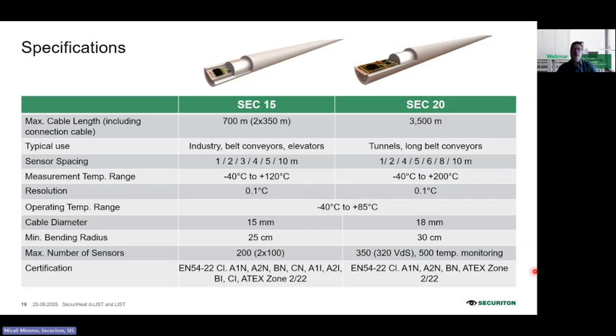We have two types of sensor cable. We call them SEC 15 and SEC 20. The SEC 15 is a little bit thinner, like 15 millimeter diameter. And here we have a limited number of sensors. They are maximum 200 sensors, or we can reach maximum with this cable 700 meters. So it means you need one controller for 700 meters, but you can expand. You can have several controllers in the same tunnel and expand every 700 meters.